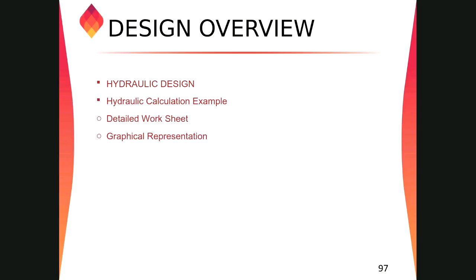So we have different hydraulic calculation softwares. The one we are going to exercise in our fire protection design is Elite software. I know you guys cannot come to the college because of the current situation, but I recommend you go to the Elite software site, I think Ahmad knows that one, and download the 10 pipe node free version. That is more than enough to perform the calculations. To understand how to perform the calculation, we'll put in 3 or 4 sprinklers with the piping changes and all, and we'll do our calculation.